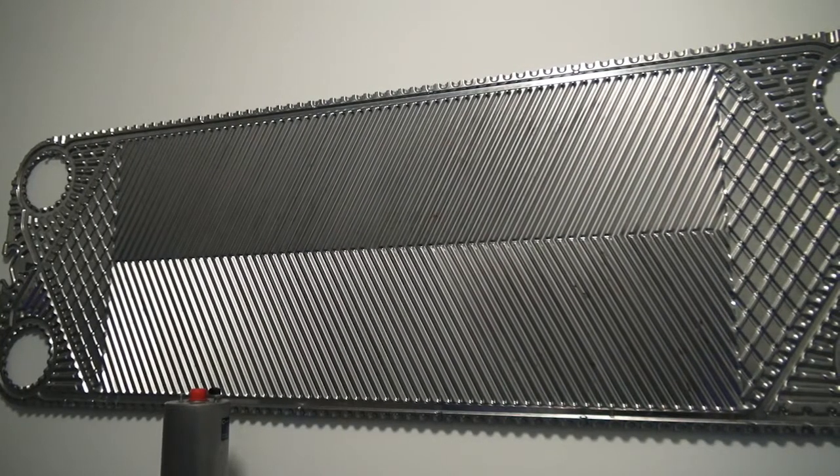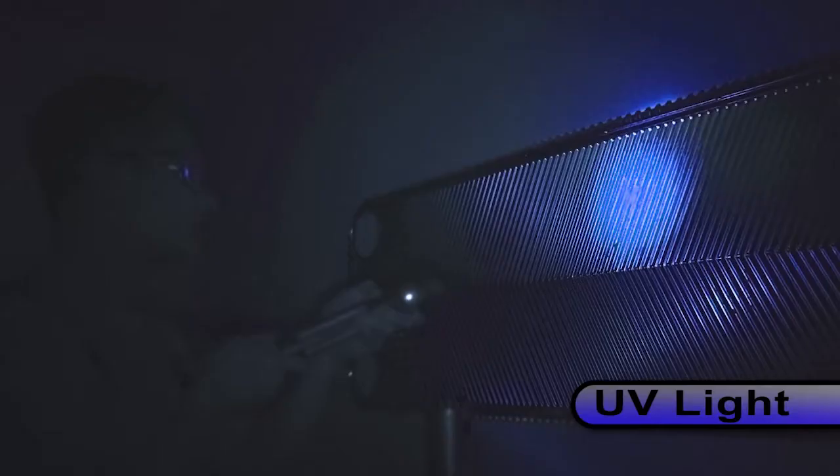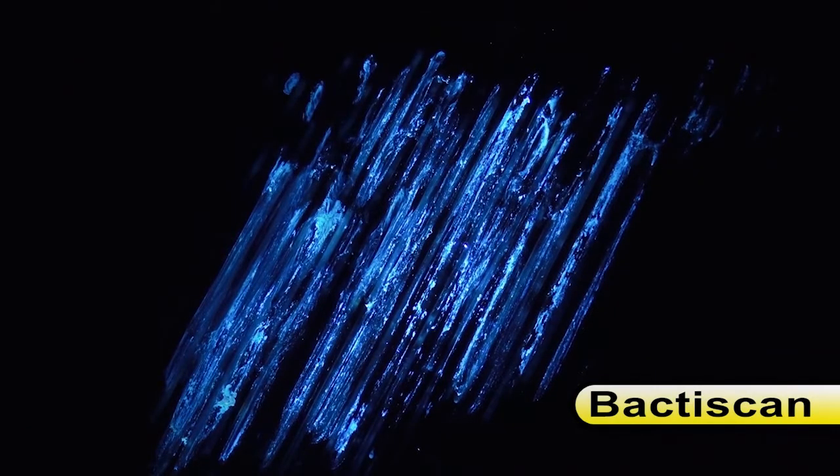These heat exchanger plates were removed from service, and under white light they look clean. Under UV light, again, there is no evidence of bacteria or contamination. But when viewed with Bactiscan you can clearly see the proteins fluorescing before your eyes.